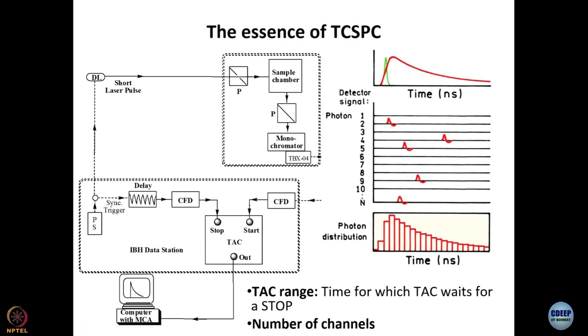The typical smallest value of TAC range I know of is 26 nanoseconds; 50 nanoseconds is more common. What kind of TAC range you use depends on what kind of decay you are looking at, because for a good analysis the decay must be complete.